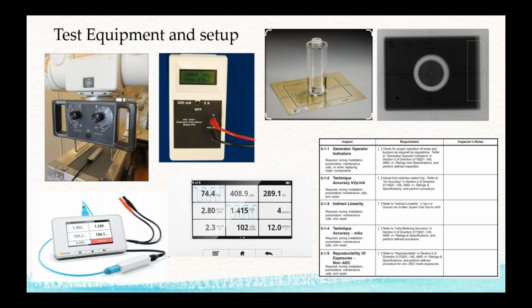Again, we're going to check the coincidence of the X-ray field to light field, and that's what you see, the little copper phantom here with the rectangular square. I'm going to close my collimator blades using my localizer light, and I'm going to use the perpendicular cone there. That's a plexiglass tube with a BB at either end. If it's perfectly perpendicular, the BBs will rest on top of each other or very close. It's hard to see from this picture, but there are two BBs in the center of that bullseye, and it's within 1% tolerance. So when my X-ray tube is vertical and I close my collimator blades, I can do a couple different tests all in one X-ray shot, right?